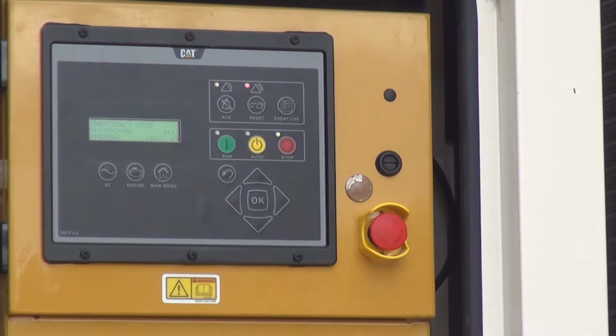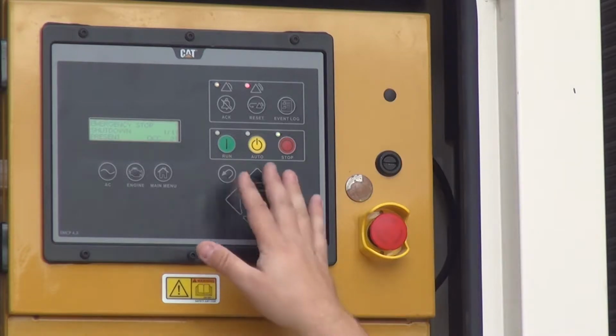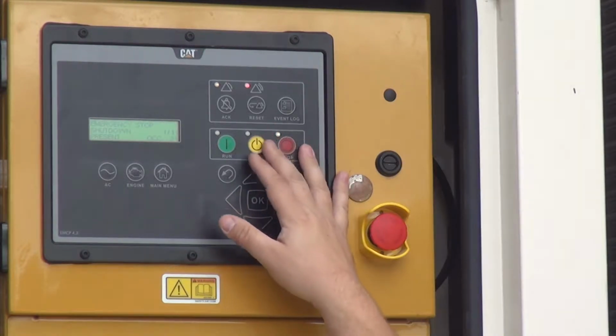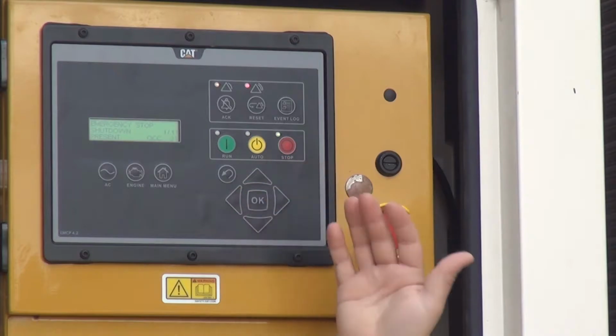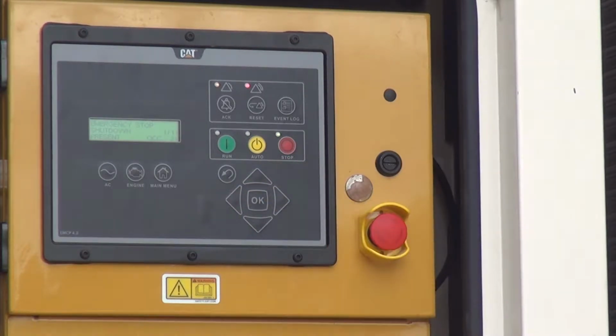So you need to fix the problem before it's going to let you reset it. It's going to force you to put it in stop to reset any code. Two reasons behind that: one, to make you stop, slow down, and figure it out. The other is that if it did shut down on a low coolant or anything else while on its weekly run, the ATS is still sending a start signal.